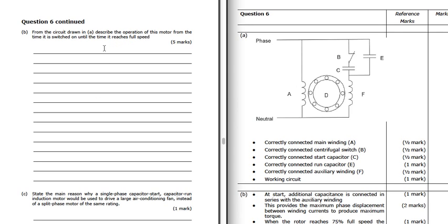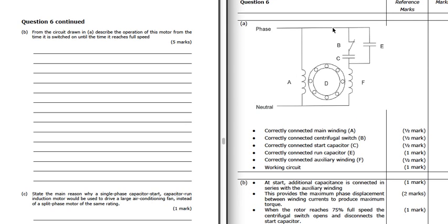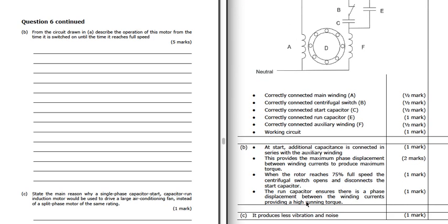Describe the operation of this motor from the time it's switched on until it reaches full speed. So when we first start the motor, the centrifugal switch is closed. The motor starts because we've got 2 windings connected together. The capacitance gives us good starting torque. When it reaches 75% full speed, this centrifugal switch will open. It will disconnect this capacitor here, and it will run on just the run capacitor. That will give us a decent running torque. So we get good starting torque, and we get good running torque.